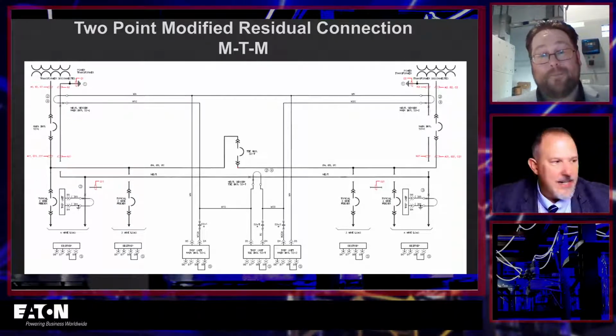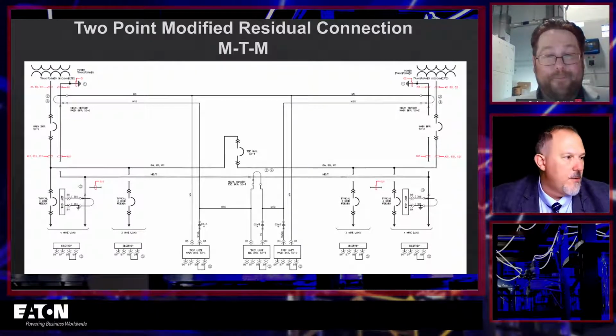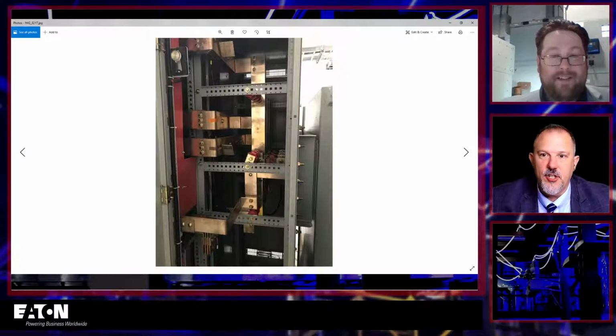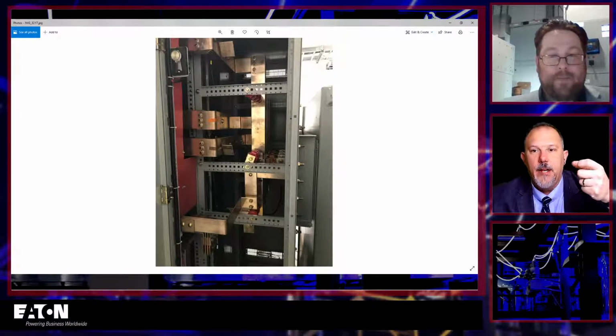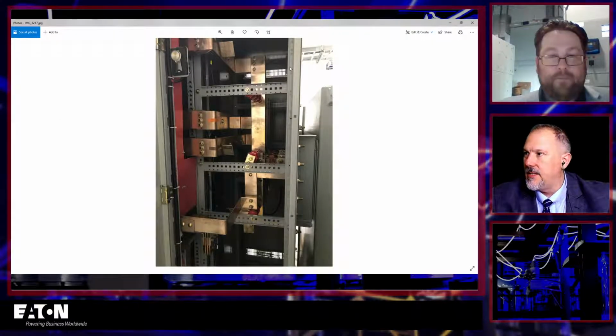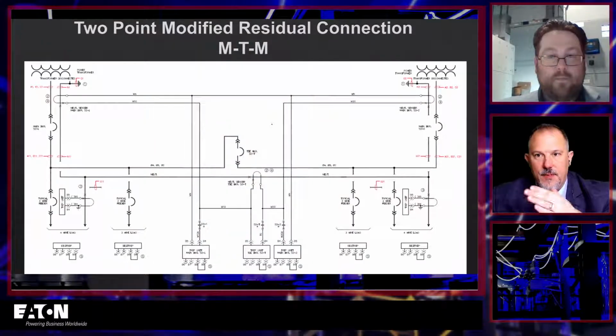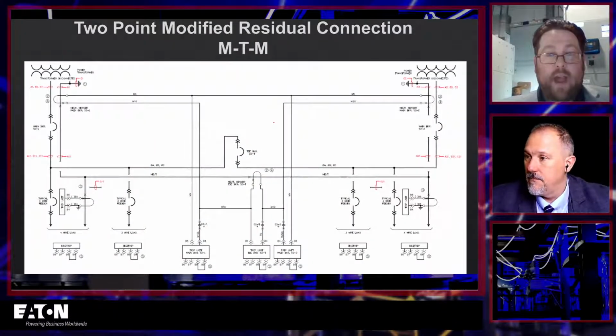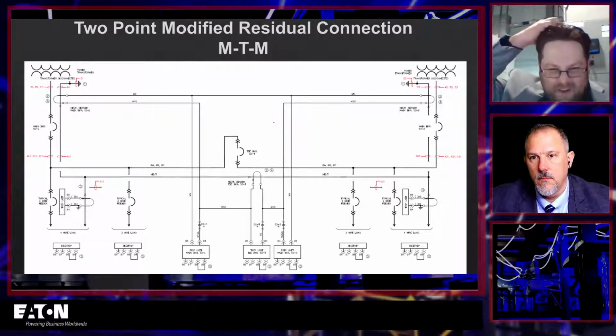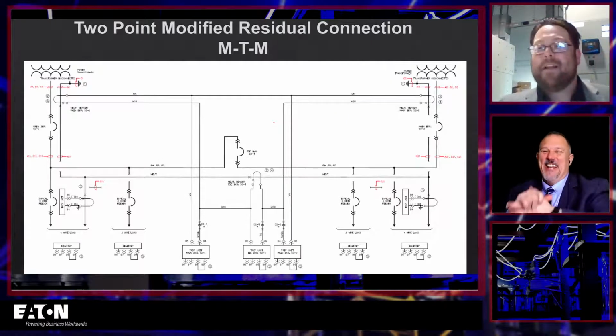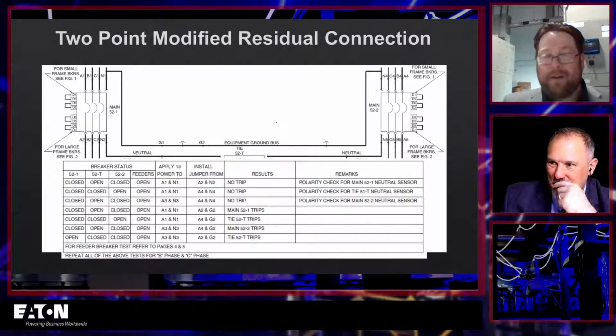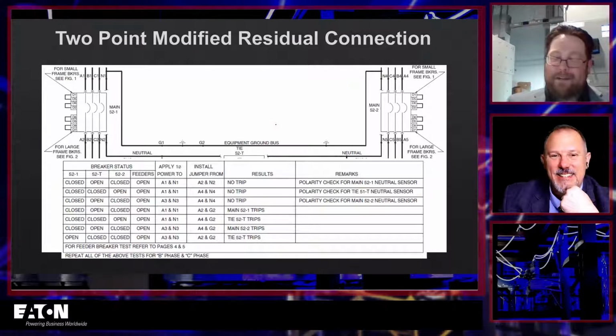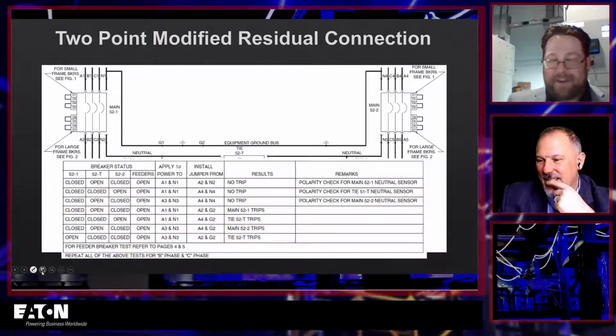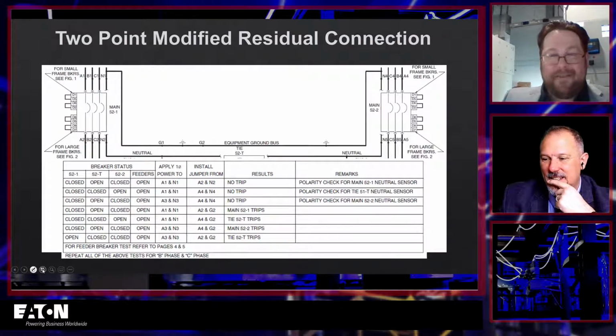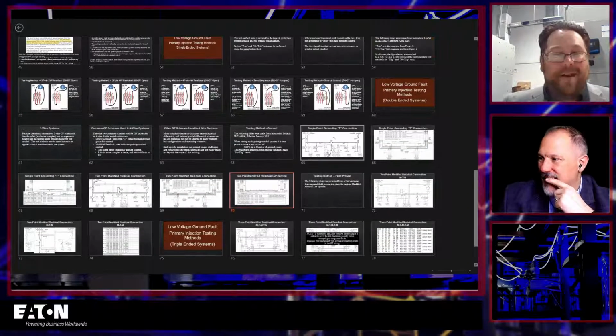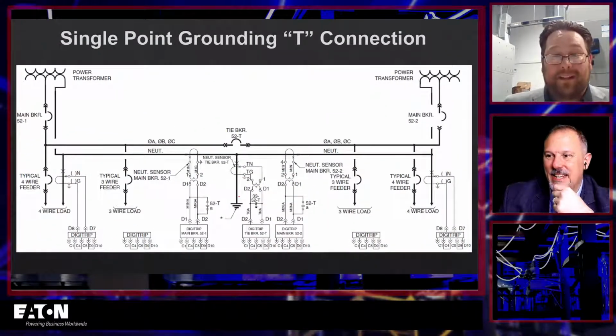Right. So you're going to take a one line diagram like that, and then you're going to walk over to a piece of equipment that looks like this, and you're going to be trying to figure out what am I clamping onto, and what do I need to isolate and all that. So you've got to make heads and tails out of both the one line and the actual physical structure to get your testing done. And Tom, I'll demonstrate what that looks like. Normally, it's a little bit of head scratching, trying to figure it out. And you're pulling out drawings, and generally, when you see individuals testing this, that first day they generally have sets of drawings laid across the table, with things highlighted and colored to show everything that's happening and figure out what this test plan really looks like in the gear.